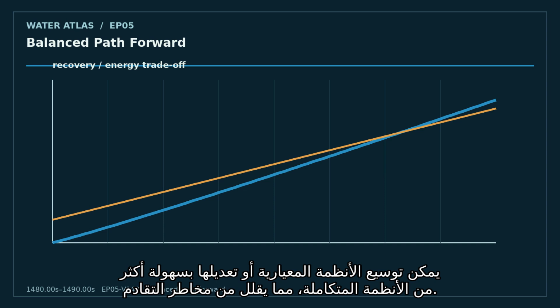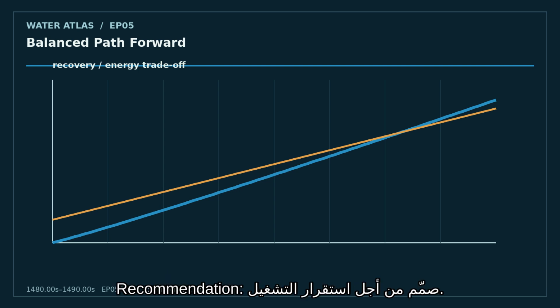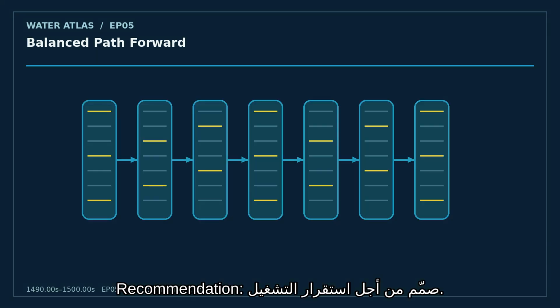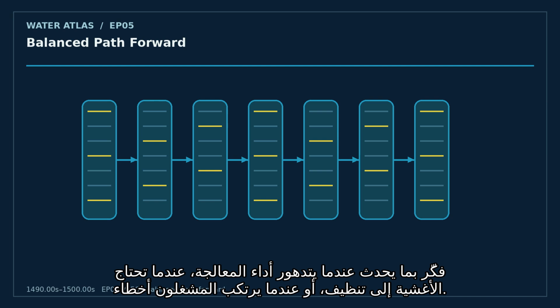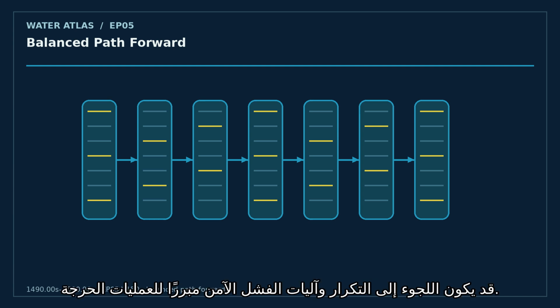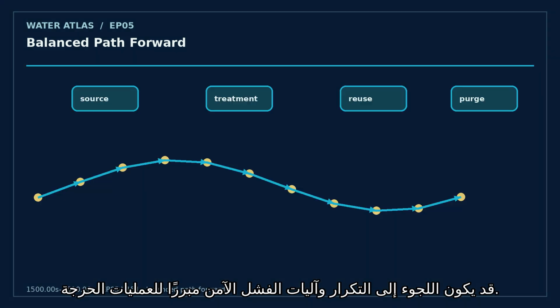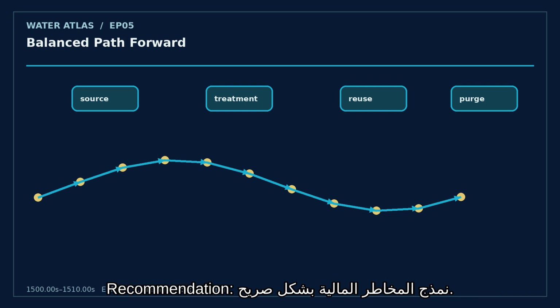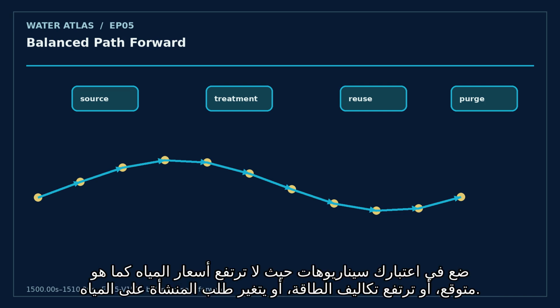Recommendation. Prioritize modularity to adapt to evolving regulations and production. Modular systems can be expanded or modified more easily than monolithic systems, reducing the risk of obsolescence. Recommendation: design for operational stability. Consider what happens when treatment performance degrades, when membranes need cleaning, and when operators make mistakes. Redundancy and fail-safes may be justified for critical processes.